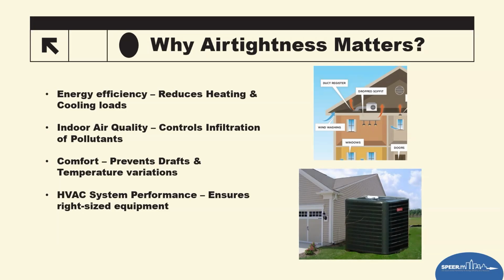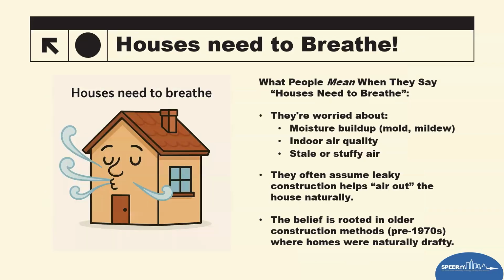Lastly, it also enhances the performance of the HVAC system by ensuring it is correctly sized and will control temperature and humidity by allowing longer run times. That usually draws down humidity and gives drier air, which feels more comfortable and colder to most people, and they can actually raise the set point on their thermostat.